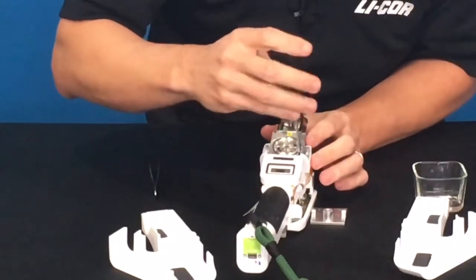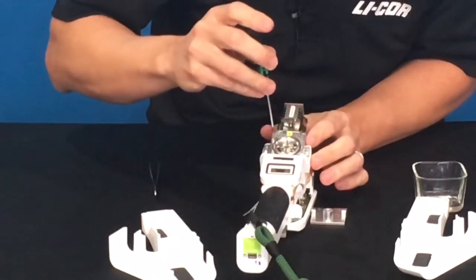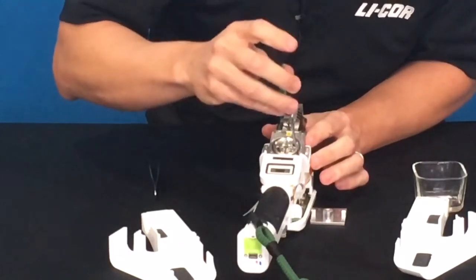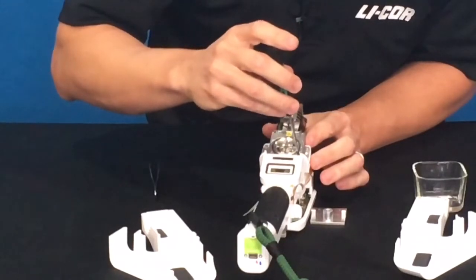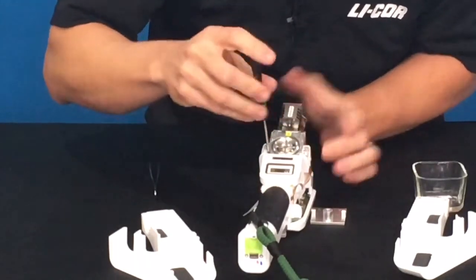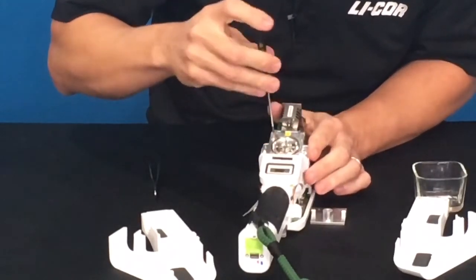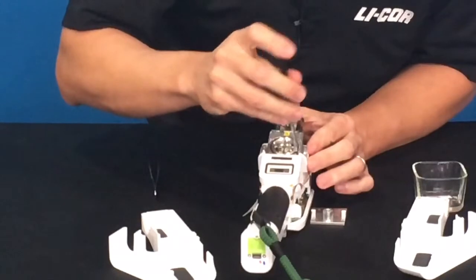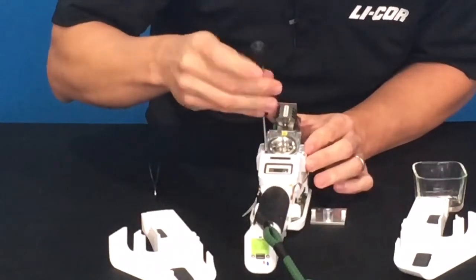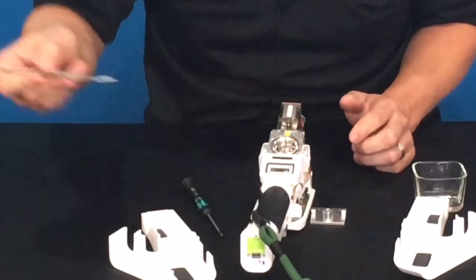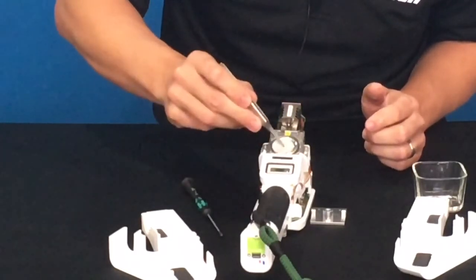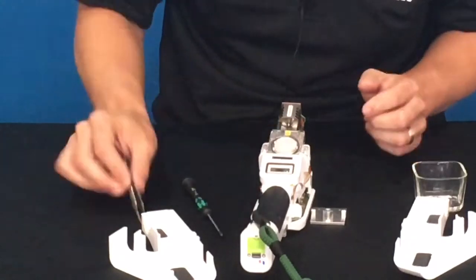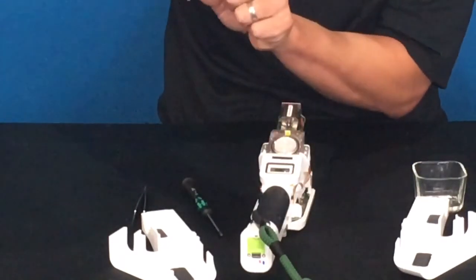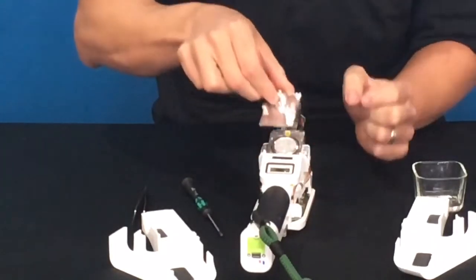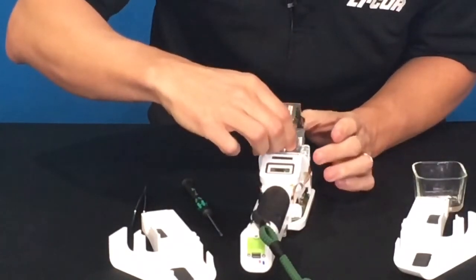Okay, and now I'll start tightening them just a little bit at a time. And you really want to focus on making sure that pump is seated properly, which it will not seal properly if it is not. So it should be obvious if the pump moves. You just won't be able to see good alignment of this component. And then you can go ahead and put the filter back if it's clean, or it can be replaced. And it's captured a little bit by this ring here. And then this part goes back on. And again, these 2 features ensure that you put it on the correct way. You can't do it backwards. It will only go on in the correct orientation.